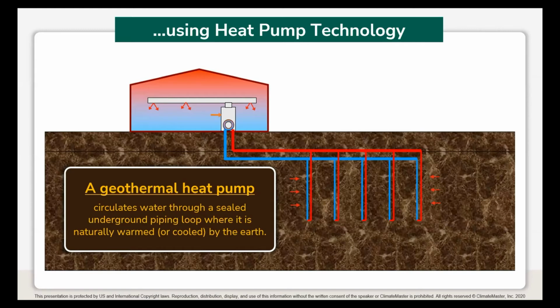Again, we are using this indoor unit with a pump to circulate water. And in your area of the world, we need some sort of antifreeze in that water. It may be methanol or ethanol or food grade propylene glycol to keep it from freezing. But that is circulated through the piece of equipment to extract or reject heat, pick up heat from the house, put it into the ground, pick up heat from the ground, put it into the house through a water-based system.